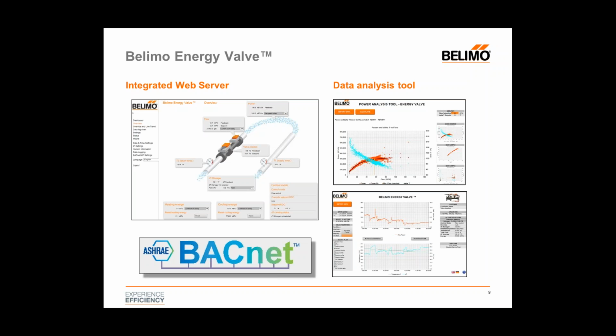You can put the energy valve in a system, run it for a while, get a load profile on that coil, extract the data set, and run it through the data analysis tool. And the data analysis tool will actually calculate a delta T set point suggestion for you to run your system at. So a very powerful tool, and all of these, including an integrated web server, are provided free of charge. There's no additional software to download for this web server. It's all integrated right into the actuator. As we talked about earlier, it's also completely integrated with BACnet MSTP and BACnet IP. So a very powerful actuator.